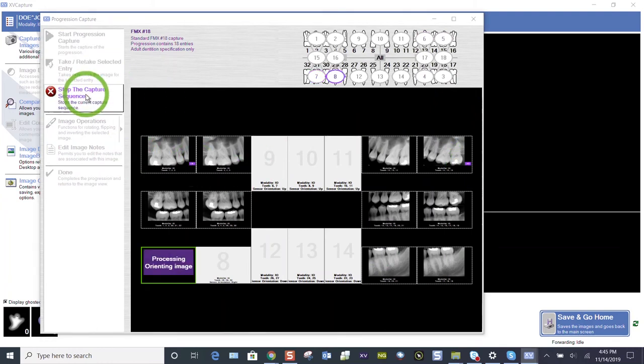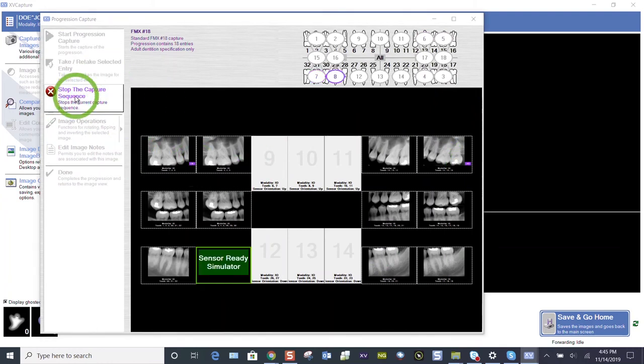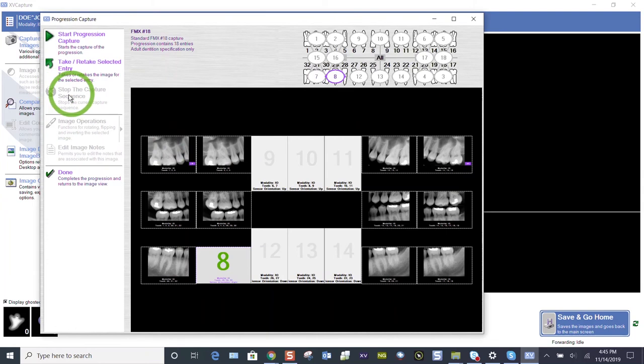So I'm going to stop the sensor. My simulator moves so quickly. Your sensor will be ready for five minutes per image. You have five minutes per image. So if the sensor times out, we're going to be looking exactly what we're looking at right now. If your patient has to get up and leave the room, go to the bathroom, take a phone call, and they're out of your room for five minutes, or if we are pulled away from our patient, that sensor will stay ready for five minutes.